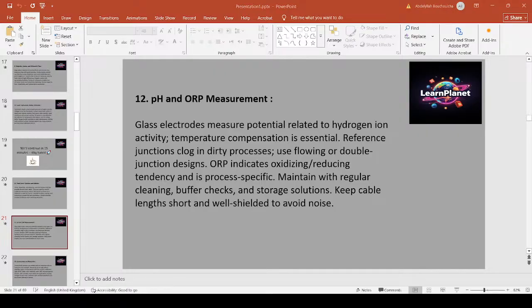Glass pH electrodes measure H plus activity and require temperature compensation and correct storage, pH 4 or KCl solution. To avoid drift in dirty or process heavy streams, foul reference junctions. Use double junctions or flowing reference electrodes where contamination is expected. ORP gives an oxidation reduction trend, not a universal contaminant number. Interpret in process context. Regular cleaning, buffer checks, and electrode replacement schedules are essential for validity. Example: in a produced water treatment skid, install a flow through pH sensor with automatic cleaning and run daily buffer checks to ensure chemical dosing accuracy.